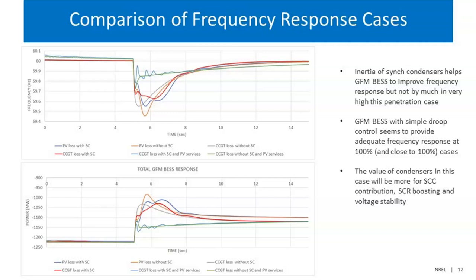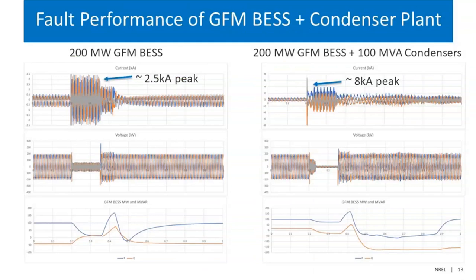And indeed, we ran a number of cases for that too. So this is the output of one plant that was exposed to a fault that happened somewhere on their 230 kilovolt line, with and without synchronous condensers. You can see that the short circuit current level in the case with synchronous condensers is much bigger, which is good for protection. And the system rides through it okay.